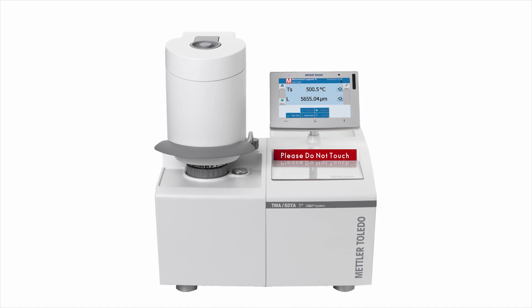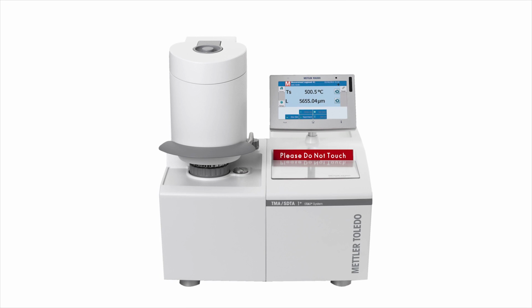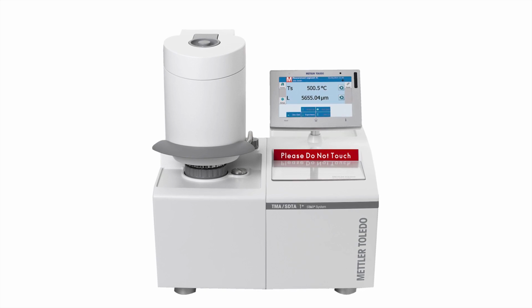In order to achieve accurate results, a TMA/SDTA has to be regularly calibrated and, if necessary, adjusted. We will now show you how to do a force and displacement adjustment and standard temperature calibration on a TMA/SDTA.